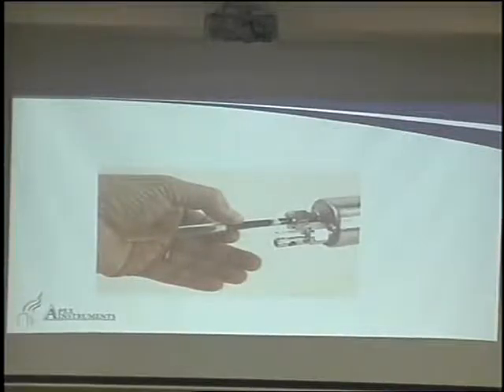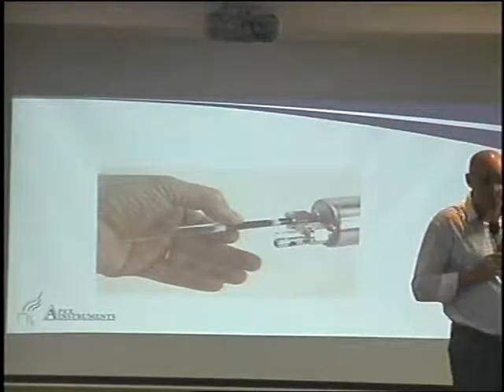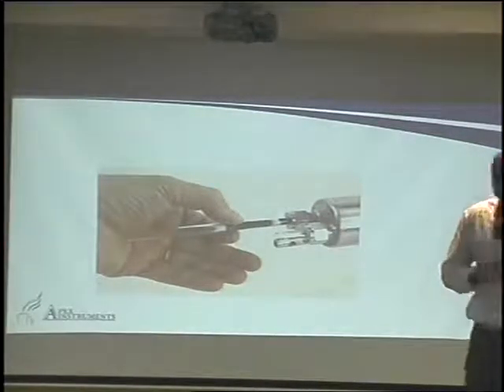So typically, you're always going to have a heated probe to guarantee that we keep the moisture away from the traps, okay? In very rare instances, if you've got a really hot source, you might actually have to do the opposite and have an air-cooled probe. Because if it's too hot, you're going to burn off the mercury and you will not get a representative sample of the emission. Maybe you need to cool down the traps to make sure we capture all that mercury when we're operating.